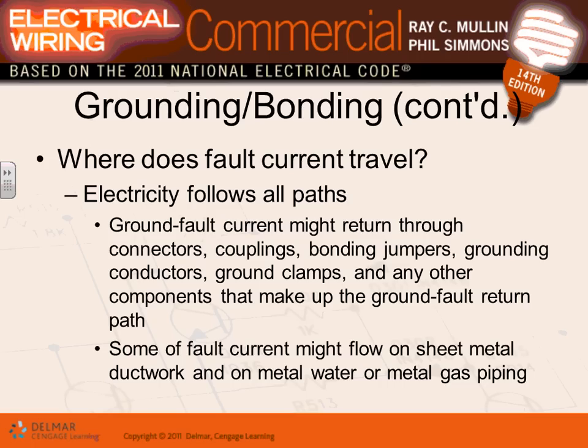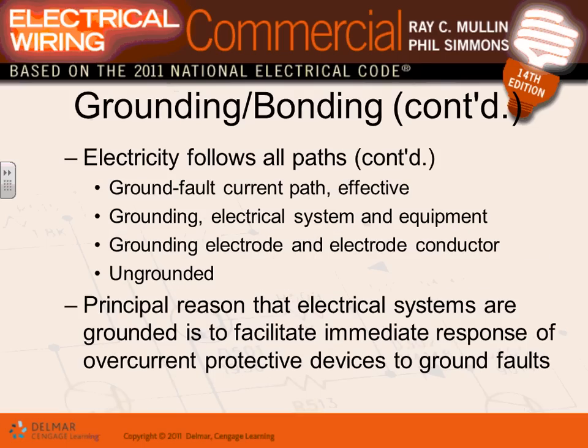So what does that mean to you and Steve and Karen when you guys torque all these lugs? It means the connectors you do have to be tight. Why do they tell you the connectors have to be tight, right? Because if you have a ground fault, the current's going to go through the conduit. Now we're going to enter the box. When you enter the box, there's a connector there. If it's not tight, what's going to happen to that current? It's going to have an impedance. Impedance means it's going to arc, and it's going to create a fire. So that's why they tell you when you're doing electrical work, you have to tighten all these connectors, right? Wrench tight, so they can carry the ground fault. So that's the whole idea, guys, of the ground fault.